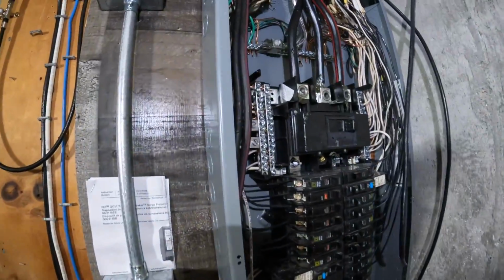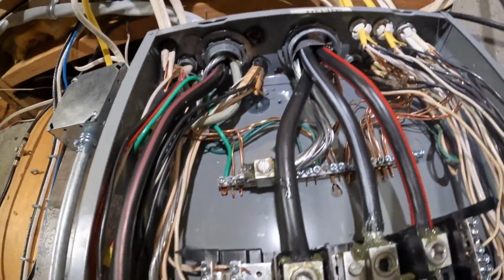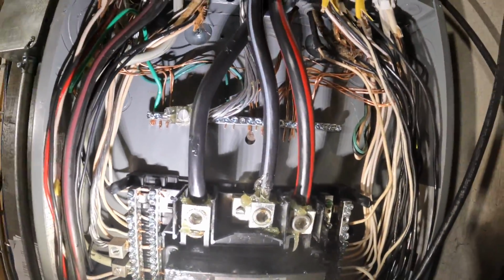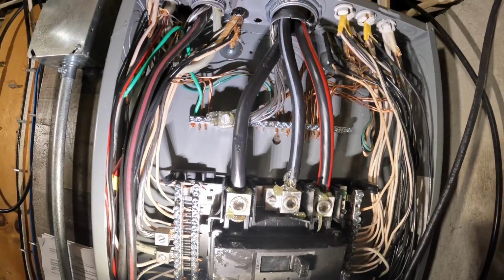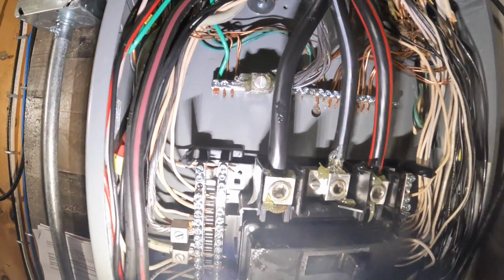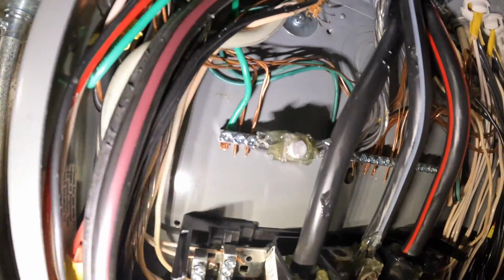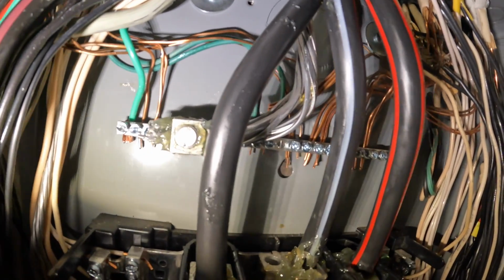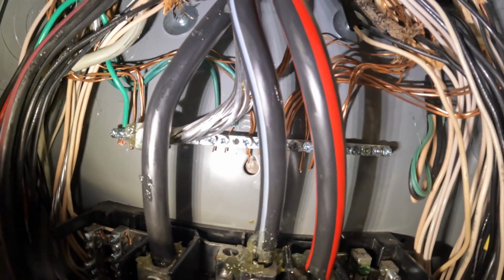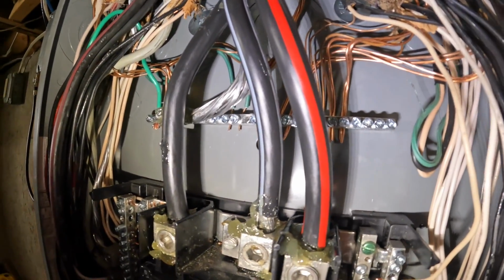The reason why we isolate our grounds and neutrals in this panel is because this becomes what's known as a sub panel. The only place on an electrical system where the grounds and neutrals are bonded together with the grounding electrode conductors to the system grounding conductor is at the main disconnect, and that will be the automatic transfer switch outside.